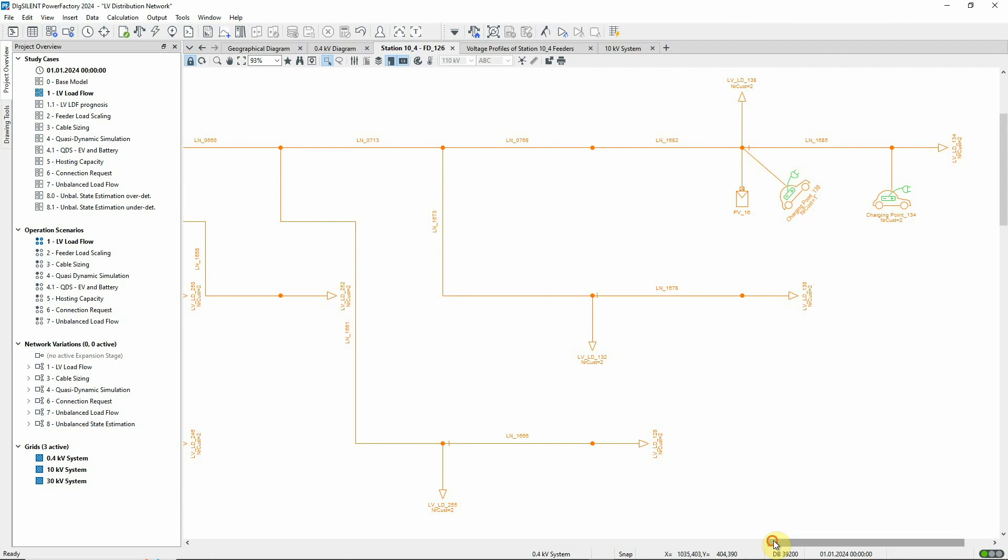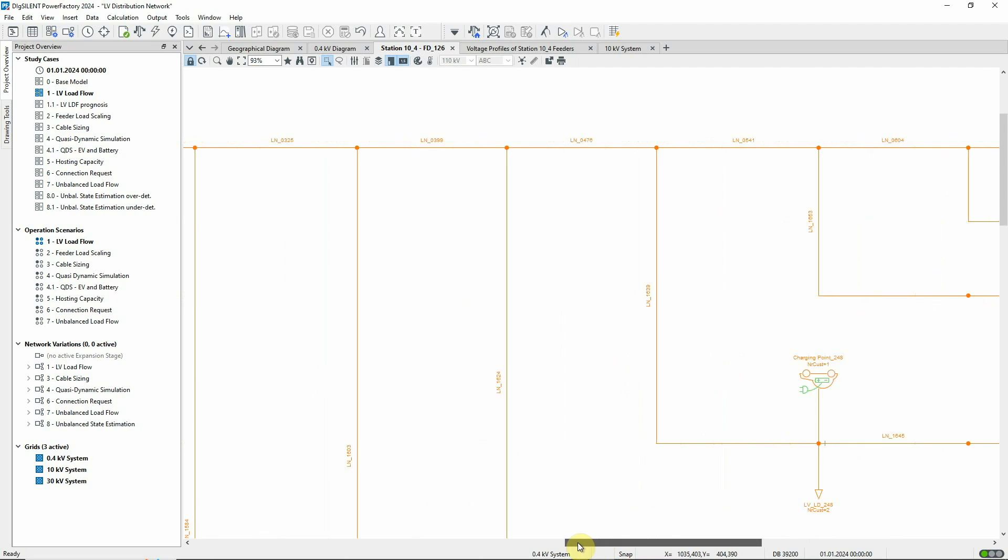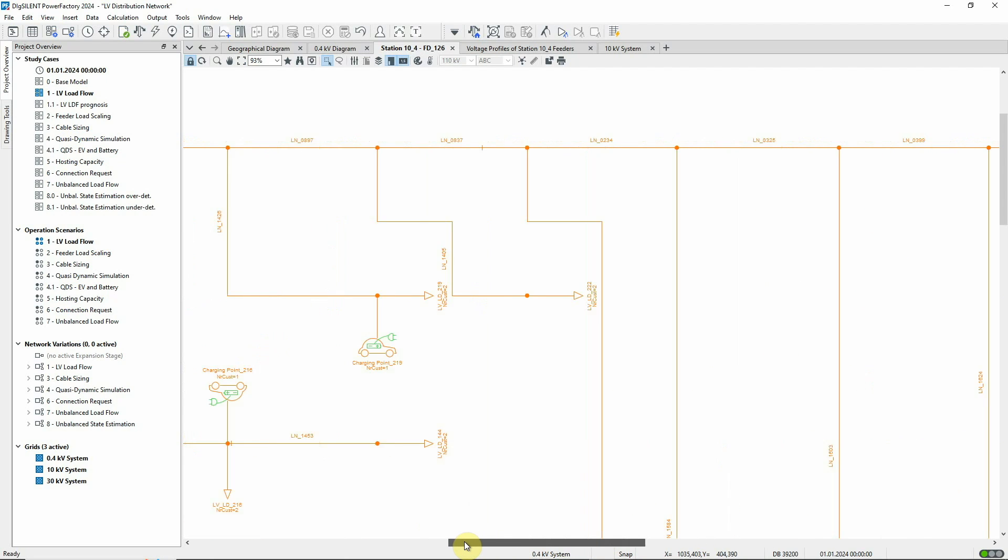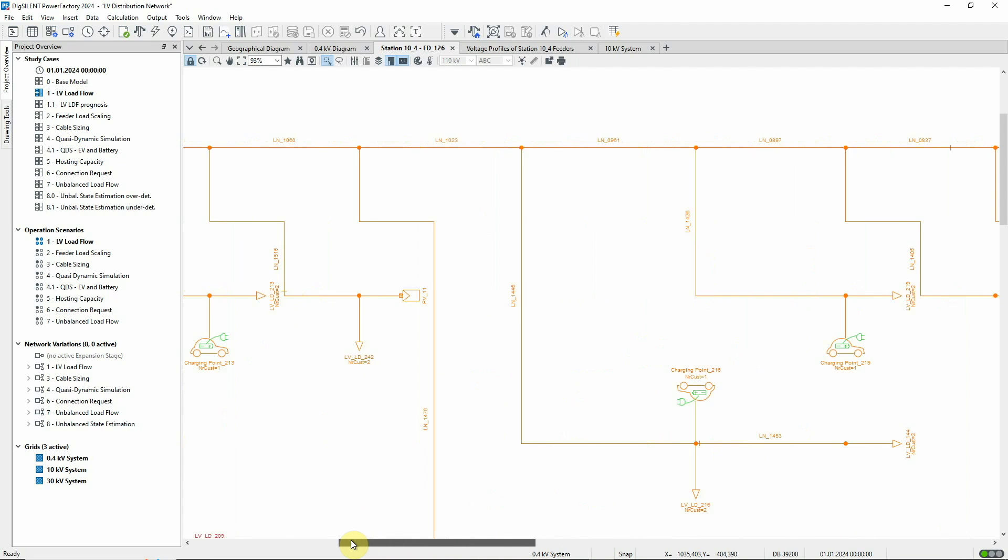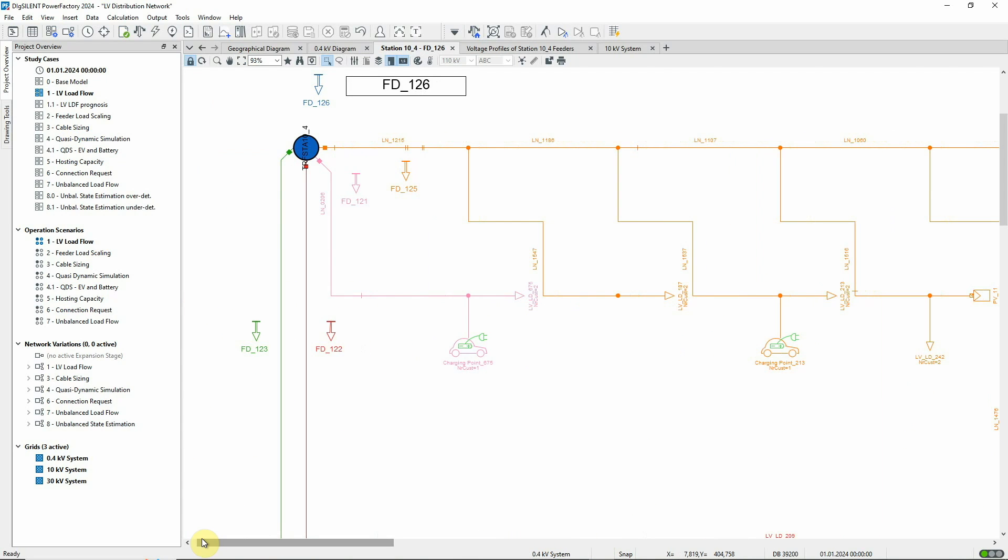Working back towards the transformer station that supplies this feeder, more and more consumers, that is more units of the same type, are included and so reduce the coincidence value. So, the more units that are supplied by a particular branch, the smaller the contribution from each unit is, to the power that must be transferred through that branch.